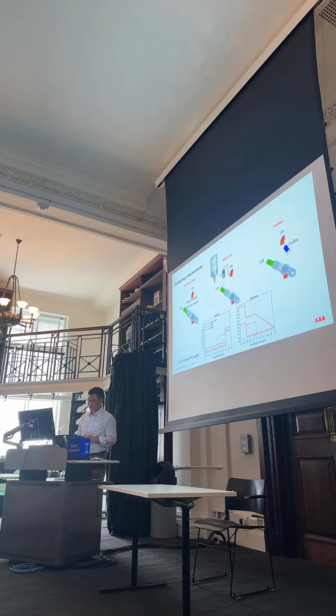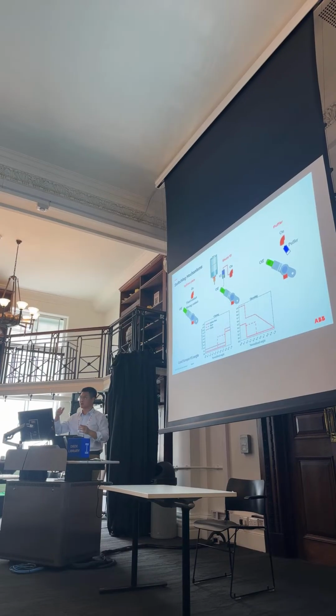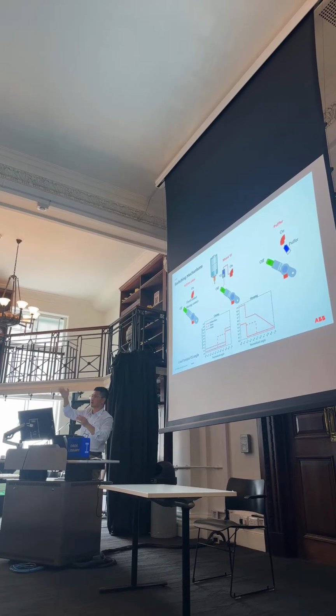Before I go to the actuator design, I want to introduce very quickly 3 kinds of switch mechanism used in load break switches currently, not only in ABB, but also in Siemens, Schneider, and other competitors. The first one, as already introduced, uses the splitter. Basically, you cut the long arc into several small pieces, and then extinguish it. That is the standard splitter blade, the cheapest version, of course.